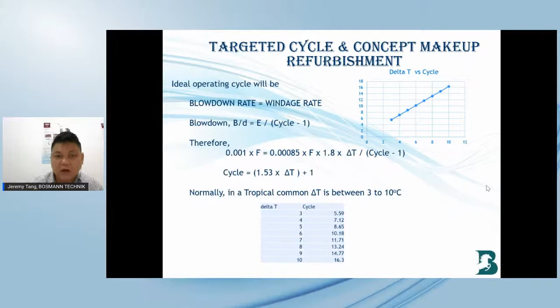Okay, for running the cooling tower at the higher cycle, we will have many risks. One of the risks is corrosion, and the second risk is scale. The risk of the concentration up to natural alkalinity in water will cause the pH in the system to reach more than 9. At that pH, biological fouling is difficult to control. It will cause many algae to grow.